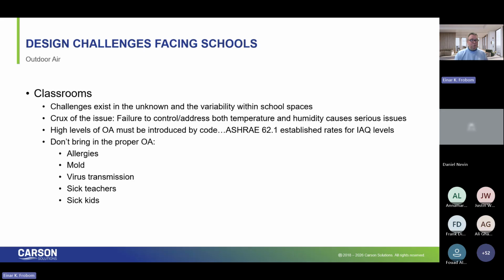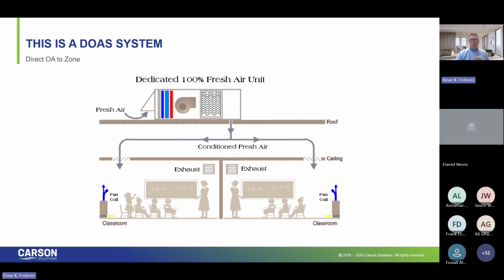But unfortunately, those things still do reside. And so one of the ways, it's not earth-shattering, but a very good and proven way to ensure that we get the right amount of outside air to these densely populated environments is to apply a DOAS, or a dedicated outside air unit, a 100% outside air handler.